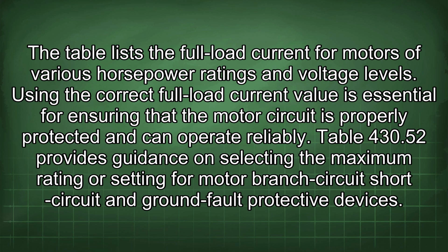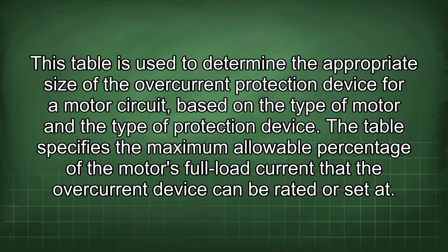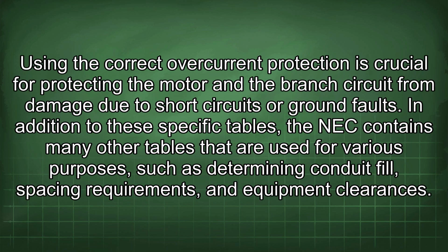Table 430.52 provides guidance on selecting the maximum rating or setting for motor branch circuit, short circuit, and ground fault protective devices. This table is used to determine the appropriate size of the overcurrent protection device for a motor circuit based on the type of motor and the type of protection device. The table specifies the maximum allowable percentage of the motor's full load current that the overcurrent device can be rated or set at. Using the correct overcurrent protection is crucial for protecting the motor and the branch circuit from damage due to short circuits or ground faults.